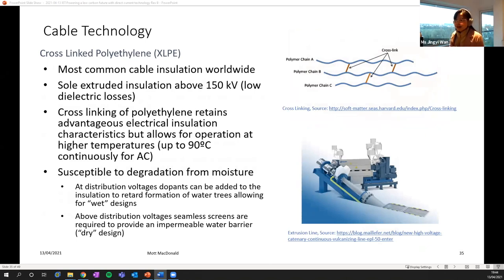And more detail about cross-linked polyethylene, which is XLPE insulation. It is the most common cable insulation, and it is the only extruded insulation above 150 kilovolt due to its low dielectric losses. Cross-linking of the polyethylene retains good electrical insulation characteristics and also allows for operating at higher temperatures, so it is up to 90 degrees continuously for AC.